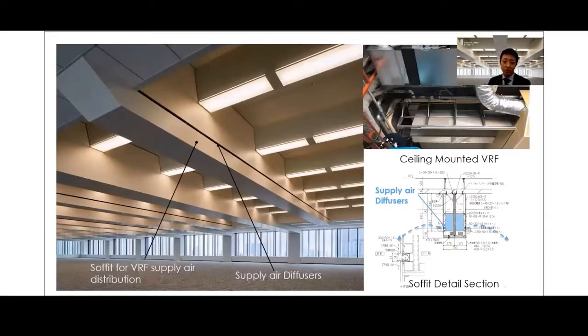As explained earlier, a water source VRF system was adopted for heating and cooling, which minimizes the thermal conveyance energy and allows optimal control according to the various usage. The supply air from the VRF indoor unit is distributed through the overhead soffit, which has an identical form to the structural beams. The soffit acts as a radiation panel for improvement of operative temperature, in addition to the effect of the underfloor distribution system mentioned earlier. This is realized with a minimum amount of customization, just with a combination of commonly available systems. Since humidity is mainly controlled by micro-DOAS, VRF control was adjusted to maintain high sensible heat operation, which results in highly efficient operation and avoids condensation risks.